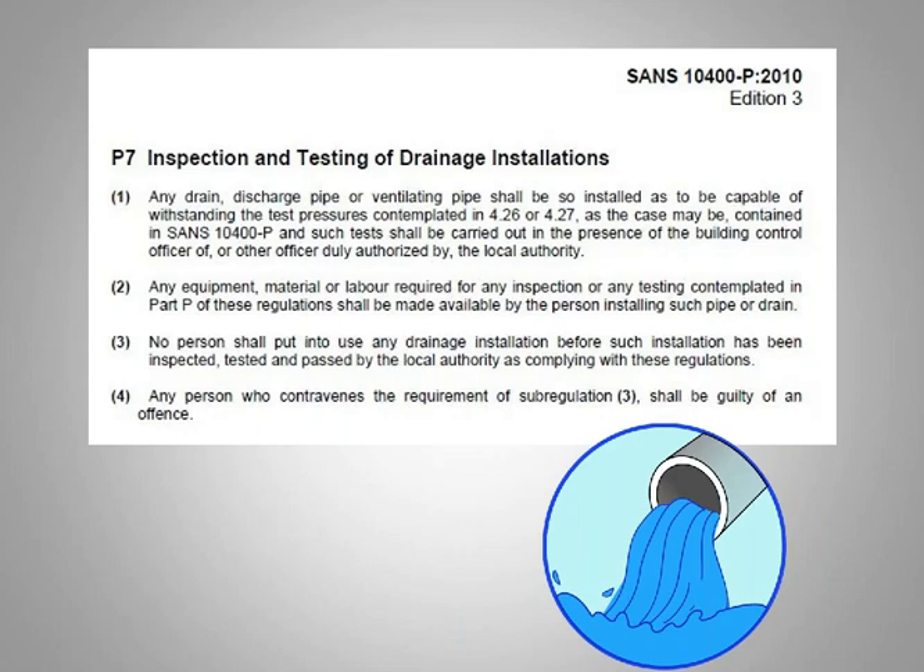The national building regulations — the document that building control uses to govern work done in the area — clearly indicates that any drain, discharge pipe, or vent pipe shall be installed so as to be capable of withstanding tests per SANS 10400 Part P clauses 4.26 and 4.27. Such tests shall be carried out in the presence of the building control officer. Even if they do not have dedicated plumbing and drainage inspectors, the local building control officer may still require you to do the test.